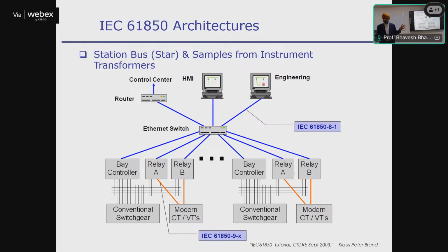It's very flexible. This is why I say they are all unique in a similar way—they're all following IEC 61850, but they're unique. You can have any unique combination. And setting up this doesn't take very long—with that tool, you can set up the whole substation in a few hours, compared to what they do now with hardwired connections and so on.